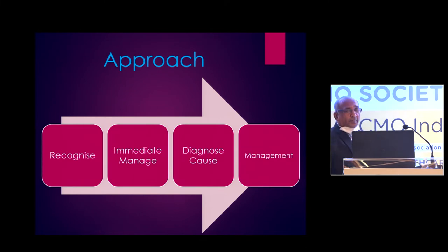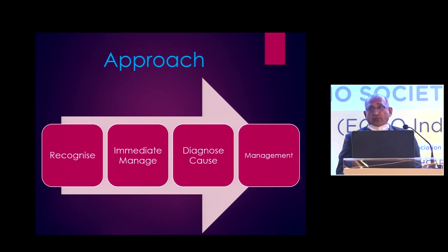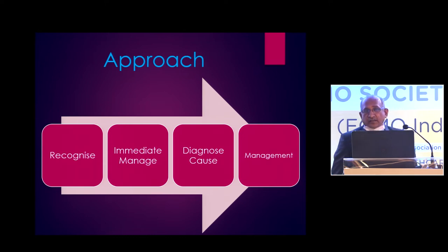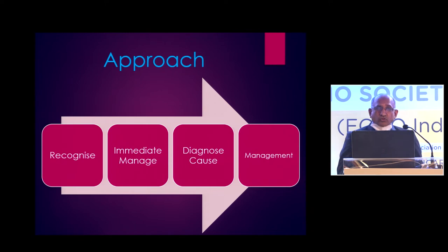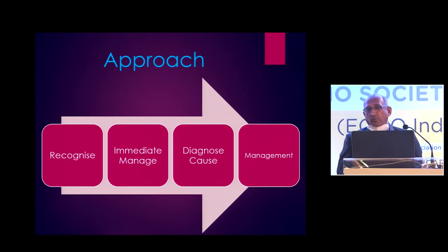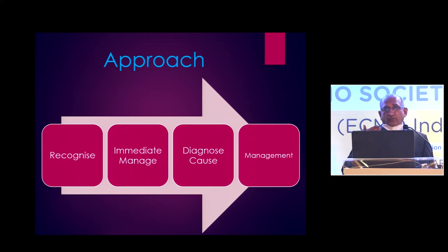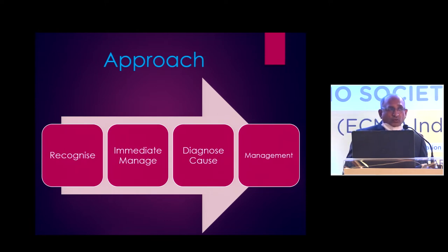What will your approach be when you troubleshoot? First is to recognize the problem — and recognition is most important before a catastrophic event takes place. For example, before the oxygenator gets completely clogged and the flow comes down, you should recognize it when there is an increase in the delta pressure. That is the most important measure — keeping an eye on circuit pressure. When the delta pressure is going up, recognize it at that stage. If you recognize it early, you can find an alternative, get everything ready, and change the oxygenator. If you only find out suddenly when the oxygenator stops, there will be a catastrophe.